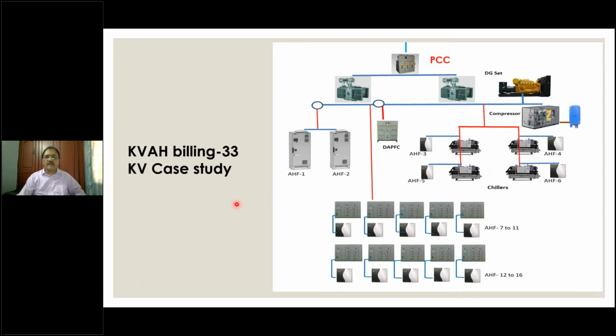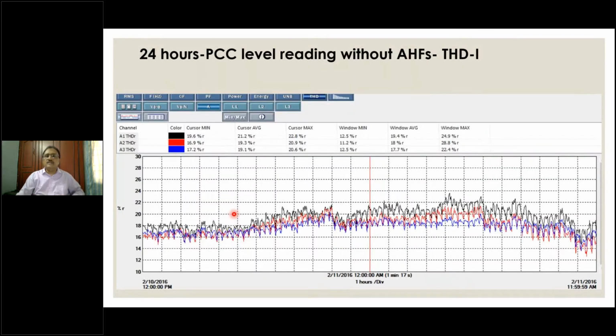The harmonic level, when I showed you, you'll understand, was very high. As you can see here, the harmonic was 19% average, 24-28% maximum. This is again a full day window, if I'm not mistaken. Yeah, 10 to 2016 to 11 to 2016. It's a 24-hour window, and we measured this value. The maximum was 28%. The average was approximately 19.4% or 19%. This is definitely not acceptable.